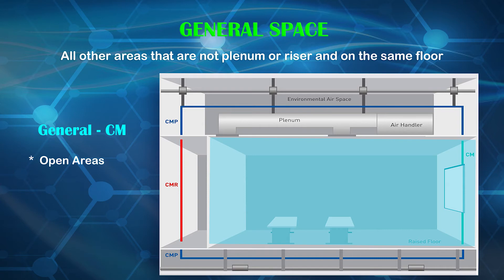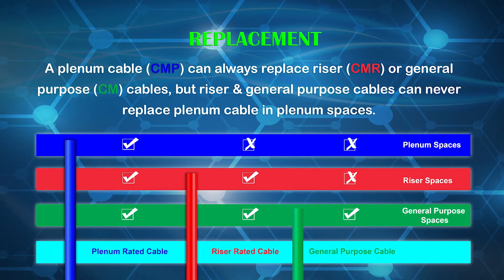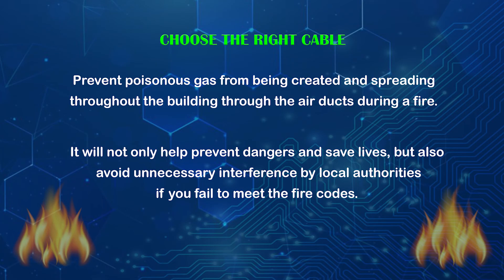A plenum cable (CMP) can always replace riser (CMR) or general purpose (CM) cables, but riser and general purpose cables can never replace plenum cable in plenum spaces. Choosing the right cable will prevent poisonous gas from being created and spreading throughout the building through the air ducts during a fire.